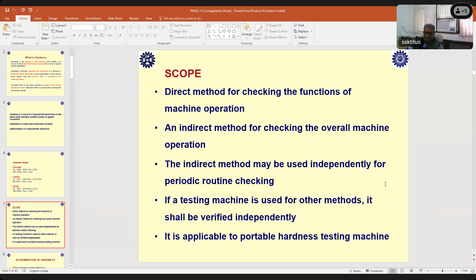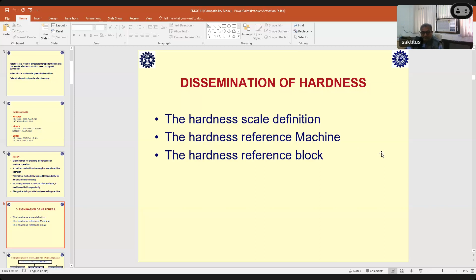Now, the hardness scale definition. I have already told you about the designation of the hardness scale. First is the definition, then the hardness reference machine, and the hardness reference blocks. This is how the dissemination from NPL takes place as far as the hardness scale is concerned. This is the unbroken chain of traceability of the hardness scale. It starts from the international definition of hardness, which is accepted by all the countries and all the NMIs, with the standard which is written, and this hardness measurement scale depends upon the national standard of force, because force is a component.